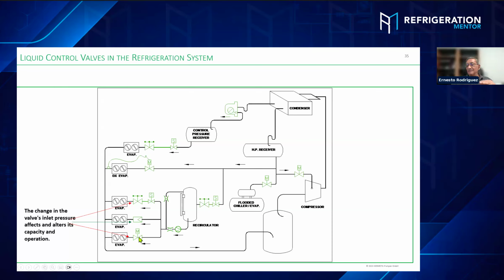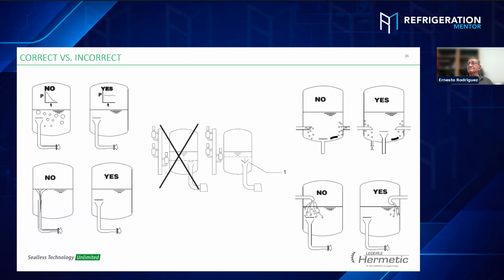The motorized valve is the same way. Normally the motorized valve stays working very softly. When you have this variation, the motorized valve starts working like crazy. Boom, open and close, trying to compensate for those pressure drops on the system. And at some point, you need to replace the motor because of overworking, or the Teflon seats of the valve. Okay, this is the beauty of the pressure control device.